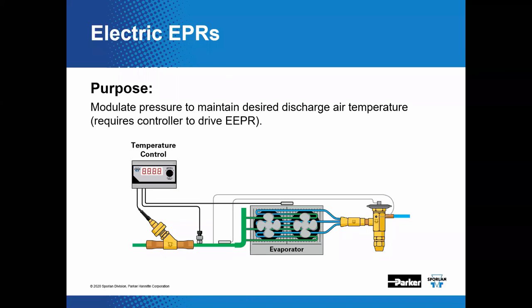We have included this slide simply for reference. In comparison to a mechanical EPR, this option with the electric EPR requires a controller of some type to accept the discharge air temperature reading from sensors, either a temperature sensor, a pressure transducer, and things of that nature.